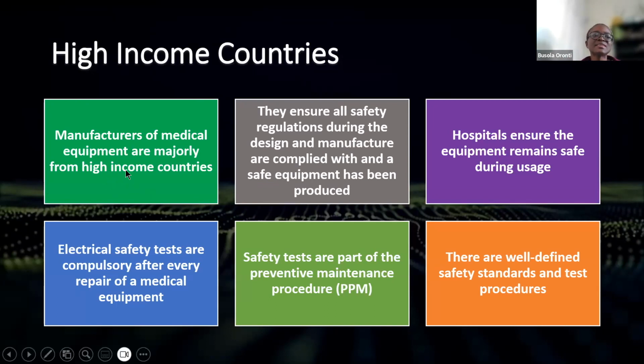Now, in high-income countries, these are the things you would expect. You have manufacturers of medical equipment, most of them from high-income countries. They ensure that all safety regulations during the design and manufacture of the medical device are complied with, and that the equipment is safe. Hospitals ensure that equipment remains safe during usage. They have very strict standards and they follow them. Electrical safety tests are compulsory after every repair of medical equipment. Safety tests are part of the preventive maintenance procedure. And finally, they have well-defined safety standards and test procedures, which we've seen.